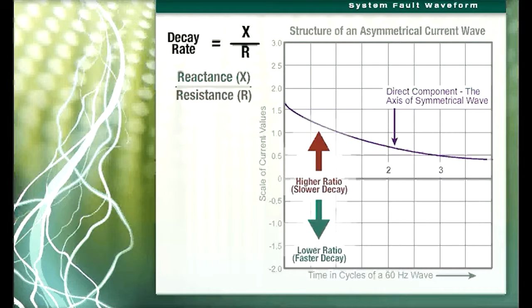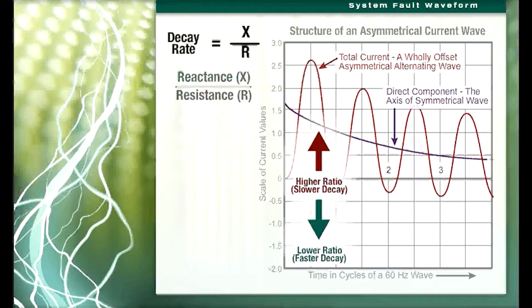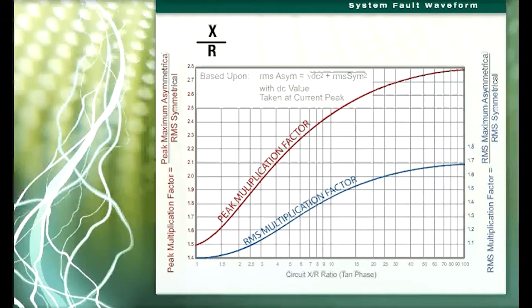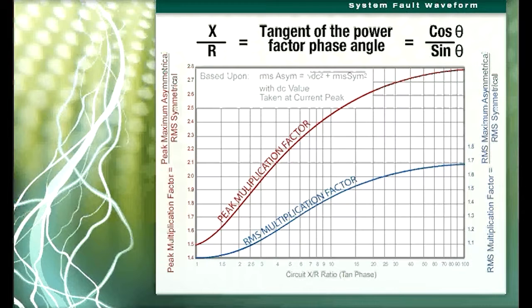The effect of this decay is that the fault current changes from an asymmetrical current to a symmetrical current with respect to the zero voltage axis within a few cycles of time. This graph shows the multiplying factors to determine RMS and peak currents for various X over R ratios. The X over R ratio is the tangent of the power factor phase angle.